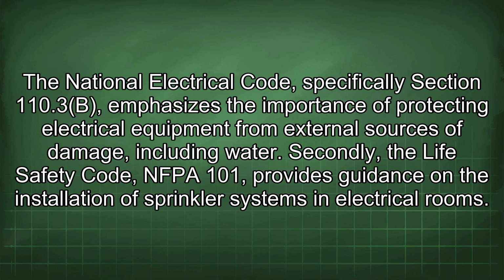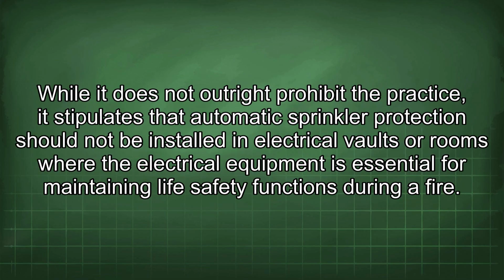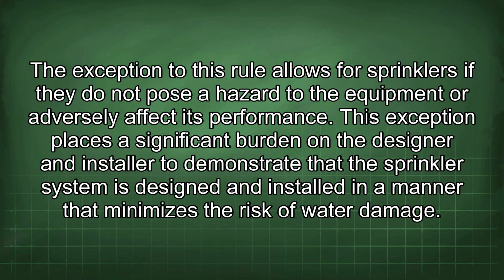The National Electrical Code, specifically Section 110.3b, emphasizes the importance of protecting electrical equipment from external sources of damage, including water. Secondly, the Life Safety Code, NFPA 101, provides guidance on the installation of sprinkler systems in electrical rooms. While it does not outright prohibit the practice, it stipulates that automatic sprinkler protection should not be installed in electrical vaults or rooms where the electrical equipment is essential for maintaining life safety functions during a fire. The exception to this rule allows for sprinklers if they do not pose a hazard to the equipment or adversely affect its performance. This exception places a significant burden on the designer and the installer to demonstrate that the sprinkler system is designed and installed in a manner that minimizes the risk of water damage.